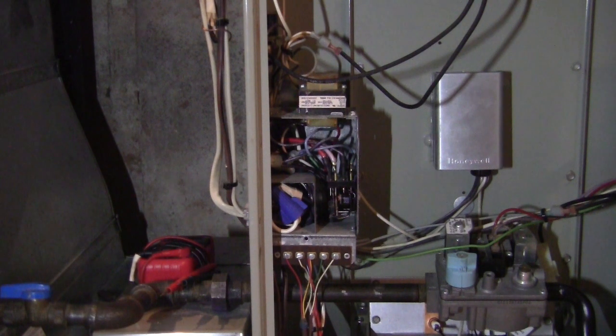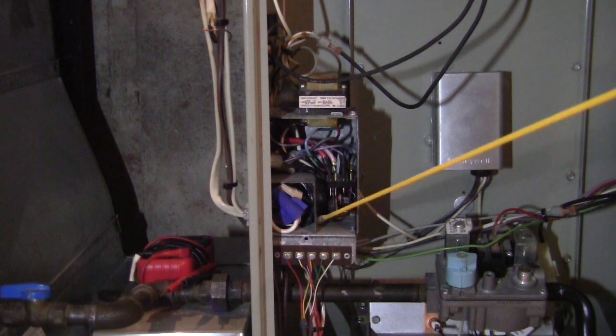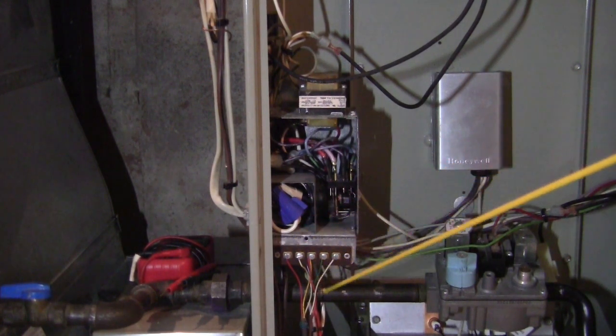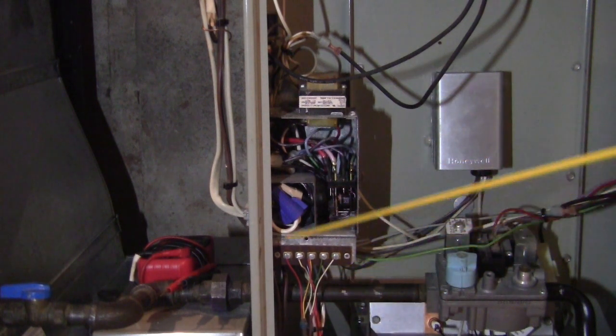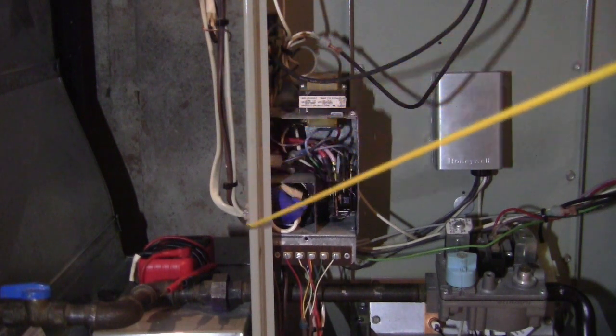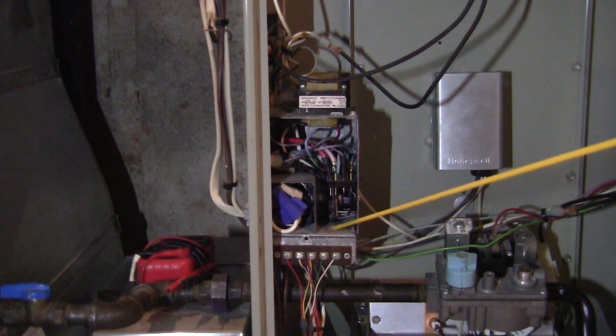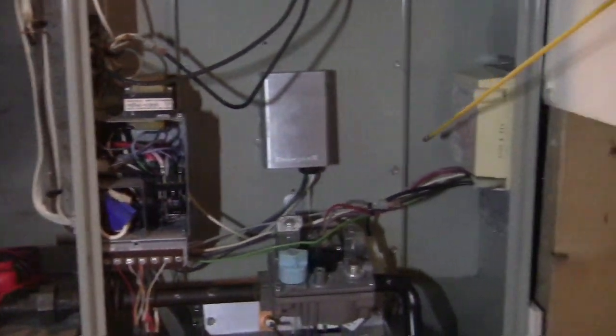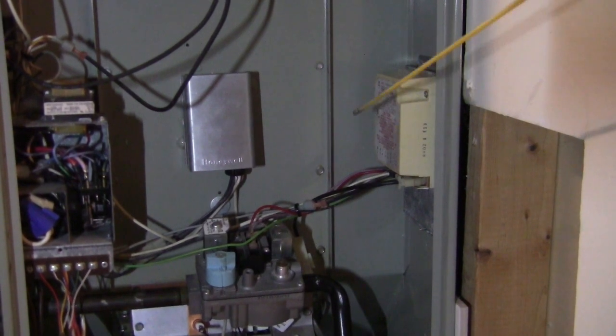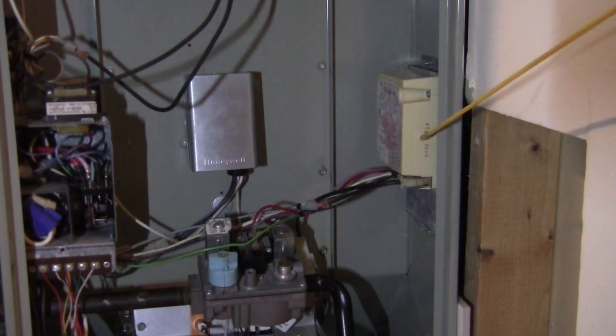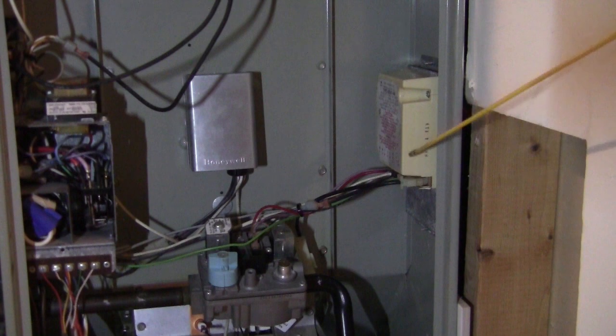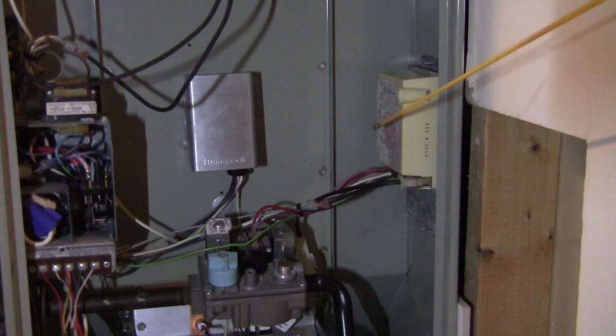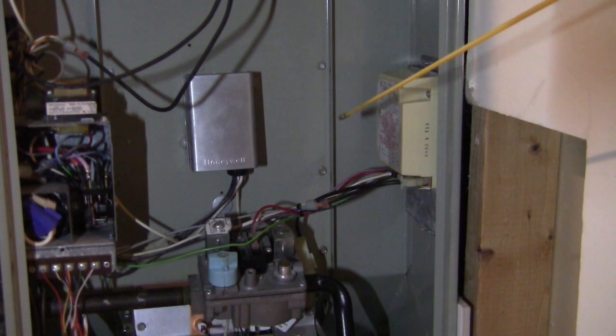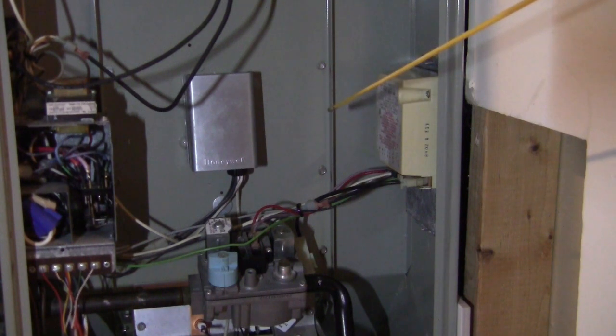degrees, the control panel will send a signal to the furnace. It's over here. The connection is from this wire connected to the upflow. You see, this is the wire from the top floor. Now, if you get the signal from here, then this one will go through this wire to here to control this unit. And once this unit senses the command from the control panel to kick in the heater, it's going to have a sequence of commands with some sort of timer, and detect some of the sensor return signals, and then make the whole thing work.